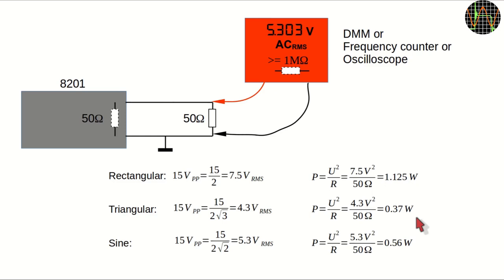This is way more than most devices with built-in 50 Ohm inputs can handle. For example, my 5334B counter calls anything above 5V into 50 Ohms the equipment danger zone. 5V at 50 Ohms means the internal terminator is rated at 0.5W. And that is also true for my external 50 Ohm terminators for use with equipments that only have high impedance inputs. If you have equipment that offers 50 Ohm termination, you should check what the maximum allowed voltage is. 5V doesn't sound like a dangerous voltage limit but in this case it is and it is already exceeded by two of the three waveforms.